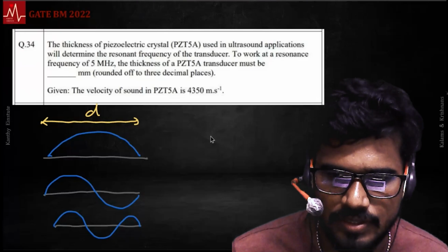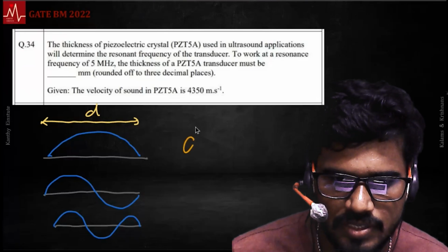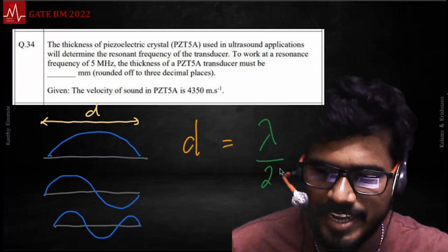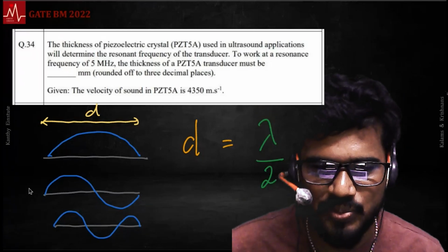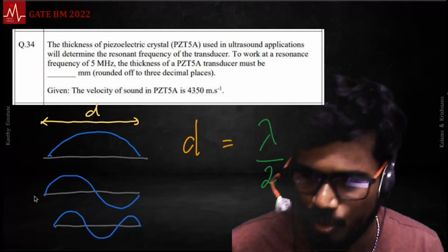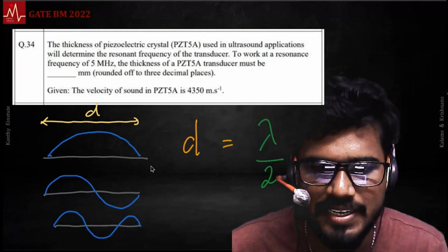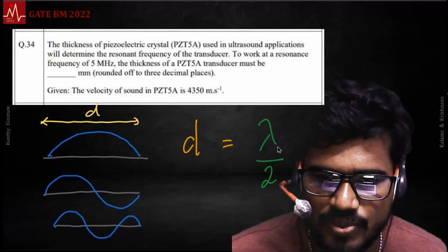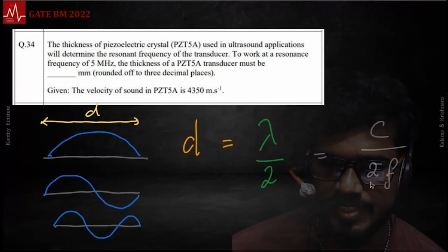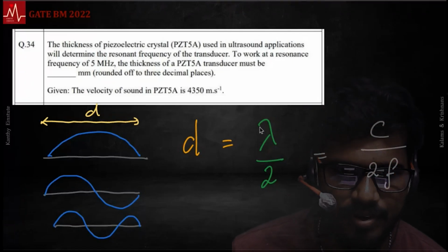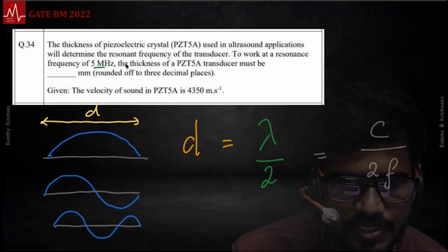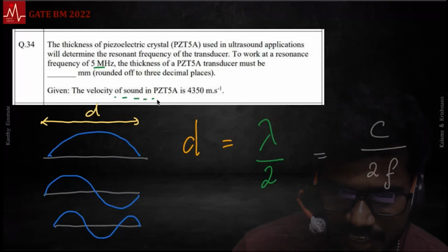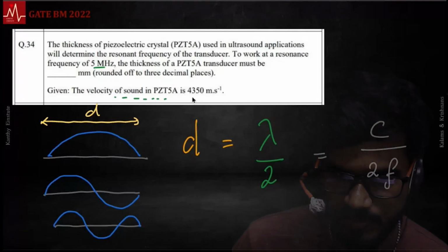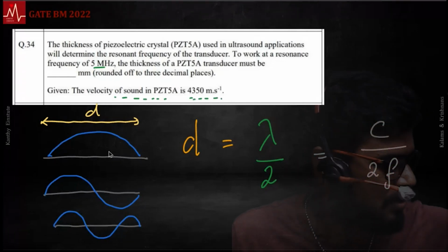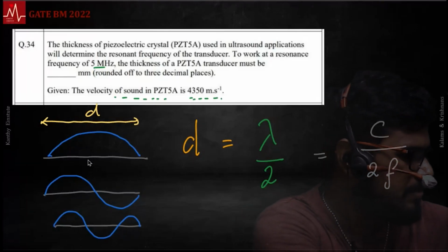So this is where we get D equals lambda by 2, the requirement for a standing wave or resonance. 2 lambda by 2 and 3 lambda by 2 are also there, but what really dominates is the first mode. So the given thickness and the wavelength are related, and you can write this as C by 2F, since lambda is C by F. F is given, C is given. Notice this is the velocity of sound in the PZT crystal, because we are now discussing the transducer itself. This wave is within the transducer; then it comes out, but the standing wave resonance is happening within the transducer.